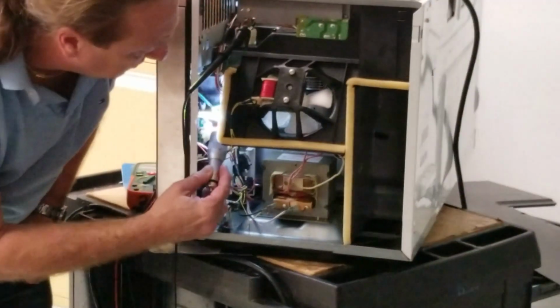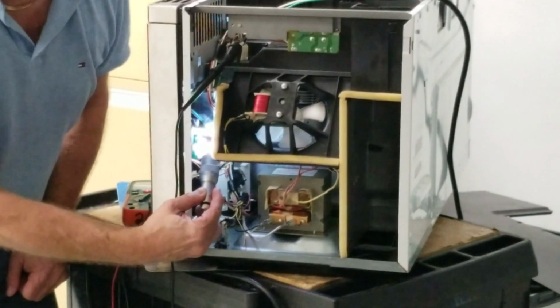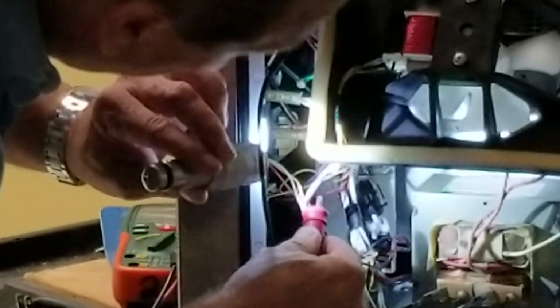It had two sets of white wires on it. If you look, this one here has got the white wires on it. I was on the one below it, which had the pink and red, the red and black. So I'm gonna go to this meter lead here, and I gotta be careful. This whole time, this thing has got live voltage, okay? So I'm gonna go to the white wire here and do that test again, because I was on the wrong wire.